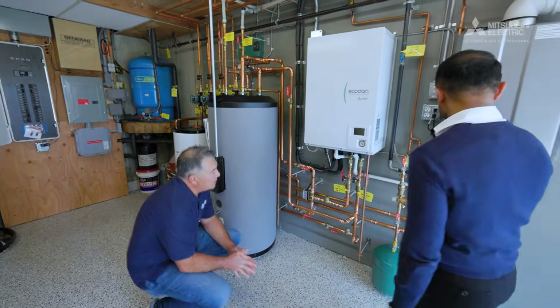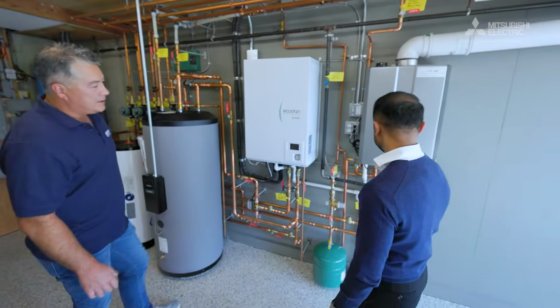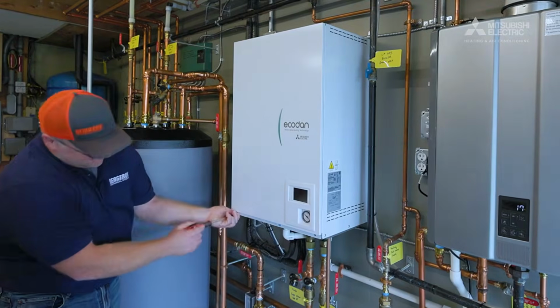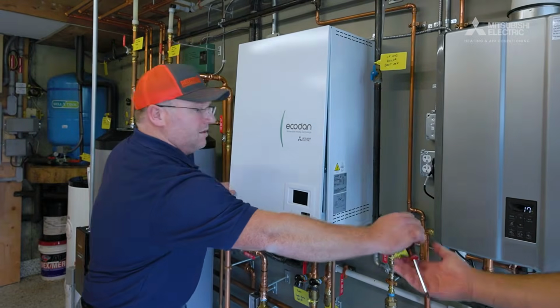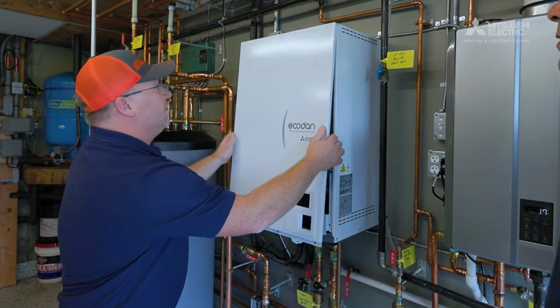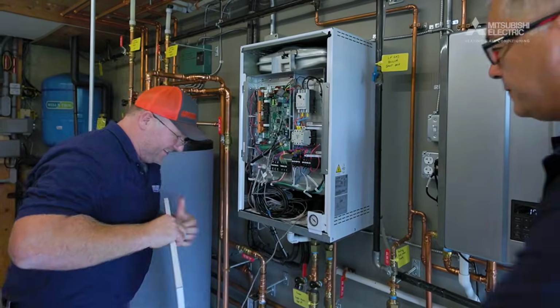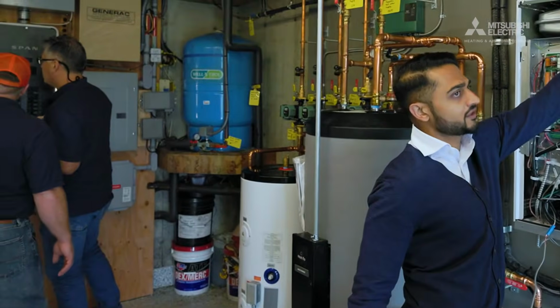Ecodan is a heat pump that's geared towards hydronic heating, cooling, and domestic hot water. It's basically an all-in-one solution, consists of an outdoor unit, an indoor unit hydro box that plugs into any existing hydronic system or any new hydronic system. You can do cooling, you can do heating, you can do domestic hot water. The number one feature that we have is hyperheating flash injection technology. What that means is 100% heating at 5 degrees Fahrenheit, guaranteed heating down to minus 22 degrees Fahrenheit, all while providing hot water temperatures up to 158 degrees Fahrenheit. So that makes it an ideal product for replacing existing boilers in high temperature heat emitter applications.